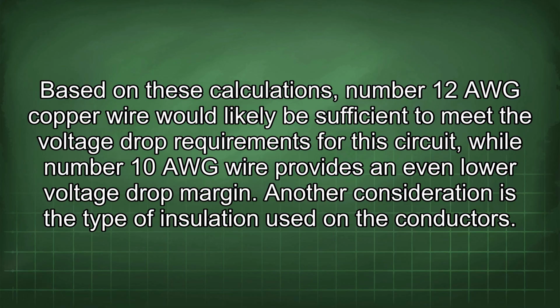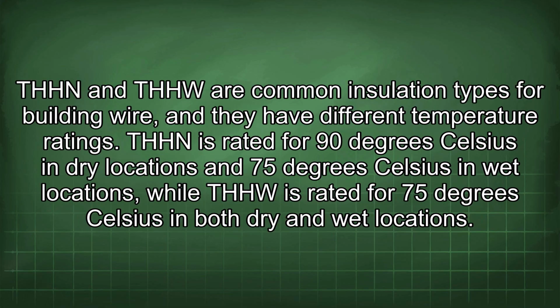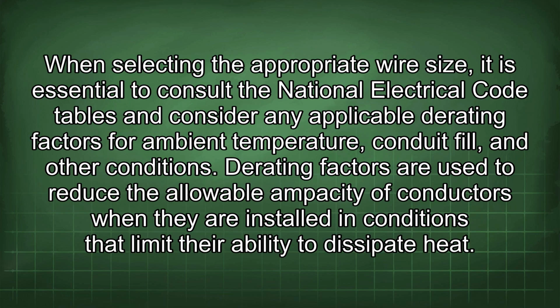Another consideration is the type of insulation used on the conductors. THHN and THWN are common insulation types for building wire, and they have different temperature ratings. THHN is rated for 90 degrees Celsius in dry locations and 75 degrees Celsius in wet locations, while THW is rated for 75 degrees Celsius in both dry and wet locations. When selecting the appropriate wire size, it is essential to consult the National Electrical Code tables and consider any applicable derating factors for ambient temperature, conduit fill, and other conditions.